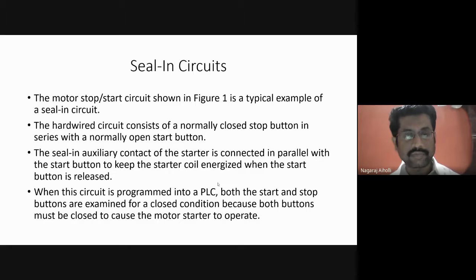When this circuit is programmed into a PLC, both start and stop buttons are examined for a closed condition, because both buttons must be closed to cause the motor starter to operate. This is an important point. When you are converting the circuit into a PLC ladder rung, both start and stop buttons should be examined for a closed condition.